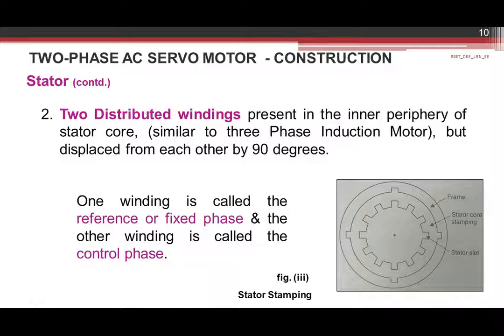The second type has a stator similar to that of a three-phase induction motor, which has a distributed winding. Being a two-phase AC servo, it has two distributed windings present in the inner periphery of the stator core, and their axes should be 90 degrees apart. The 90-degree separation is needed to produce a rotating magnetic field. One winding is called the reference or fixed phase and the other is called the control phase.